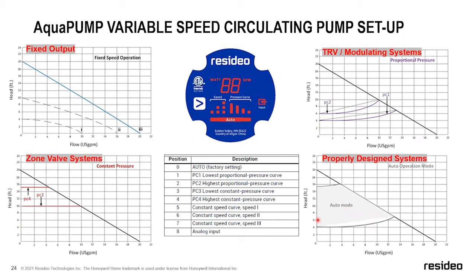What's going to happen is the pump will float inside of this curve based on the different dynamics inside the system. And we're going to keep the pump conversation a little high level, because if I went into extraneous details, this would end up being a 5-hour pump class. So I'm going to touch on what these different modes mean. If you have any additional questions, feel free to reach out to any of your Resideo reps and we can answer those for you or dive into more detail.